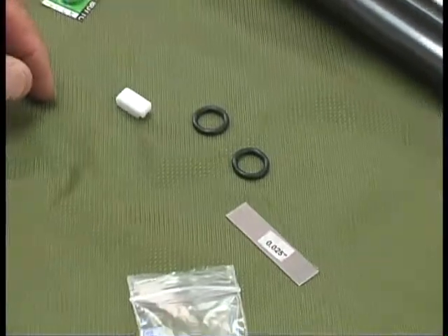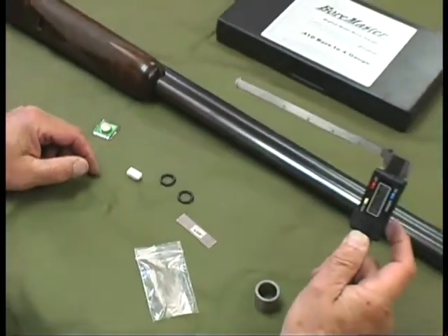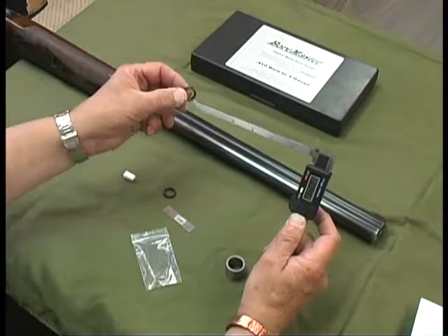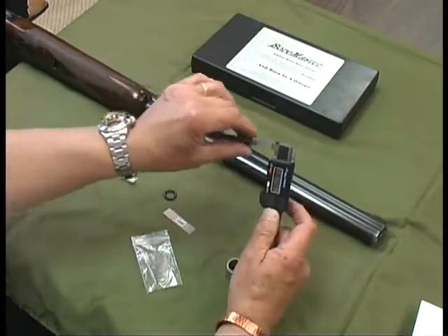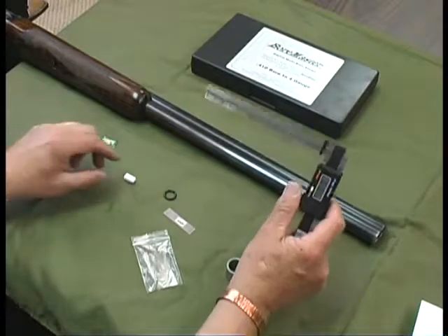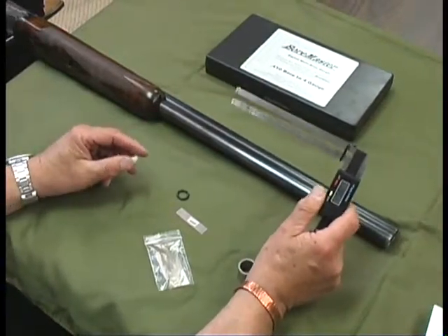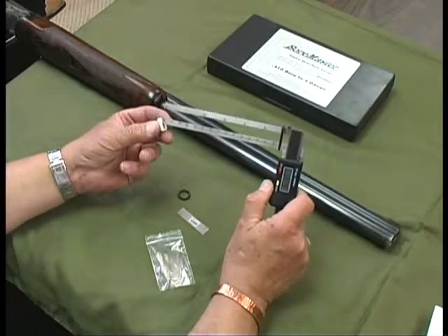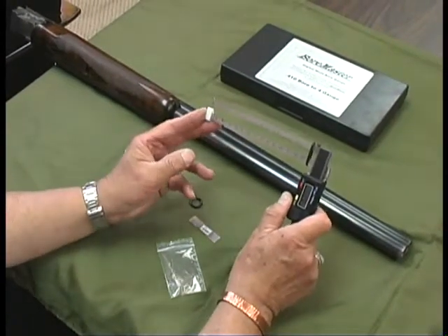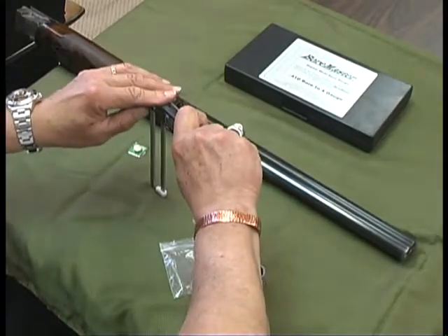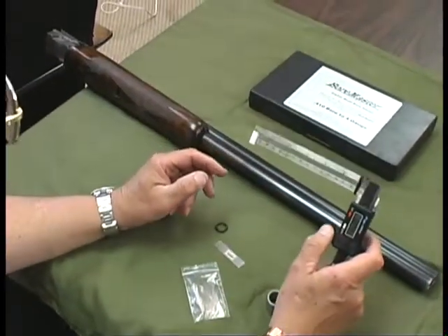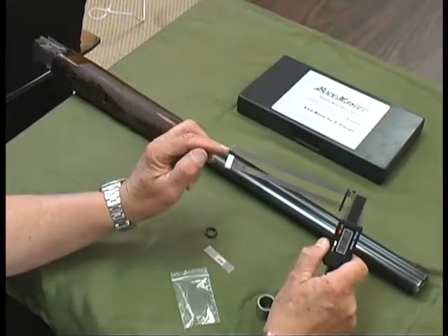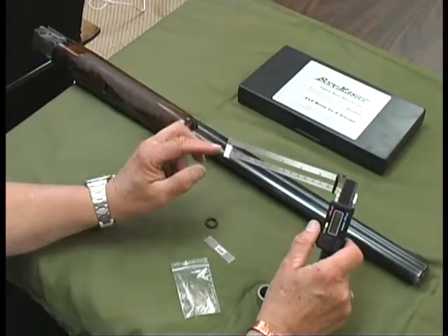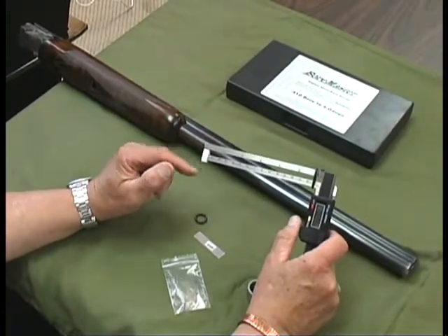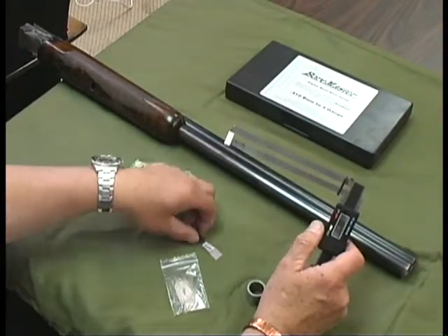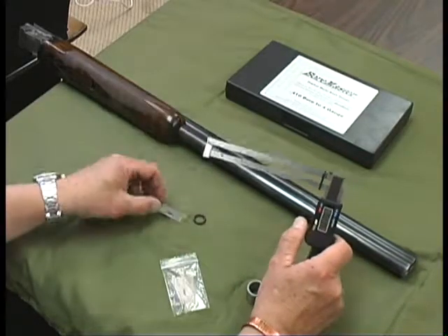Now to use the BWT device, you simply compress the BoreMaster spring so the two probes are together, and then put the O-ring right on the probes. And then we pull the probes in the open position in the opposite direction of the standard spring, and we push on the BWT device. Sometimes it's good to just get it straight by pushing it down on the table like this. As you can see, this third bead and the top of the BWT device are now reading together. So what we've done is essentially we're capable of reading this barrel wall dimension here.